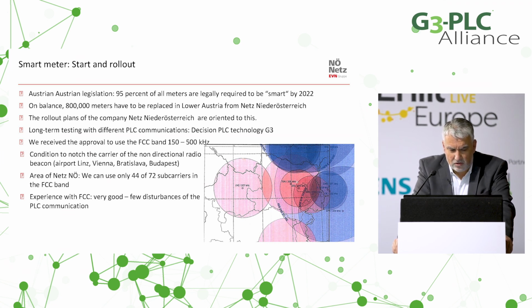We have the condition to notch the carrier of the non-directional beacons, the radio beacons of the airports around our district. This is Linz, Vienna, Bratislava, Budapest, because these non-directional beacons have frequencies in this range. This means that Netz Niederösterreich can only use 44 of the 72 subcarriers in this FCC band. But our experience with the FCC band is very good. We have few disturbances of the PLC communication.